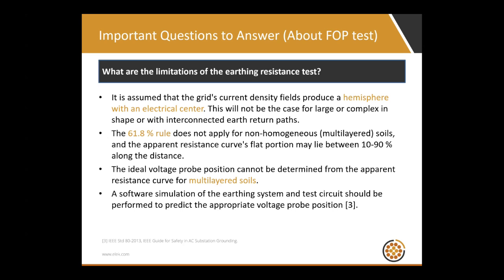The mathematics behind the Fall of Potential test are extremely complex, even though they are simplified or idealized. Still, the derivation is really, really complex. We won't get into it here. If you are interested, you can refer to IEEE Standard 80, and there are the original references there. You can look into the derivations. A software simulation of the earthing system and the test setup is really ideal, can easily be done with your design or modeling software, and it can predict the results of the test. It can also provide guidance as to your test setup and where you should ideally be running the voltage electrodes or the voltage probe.